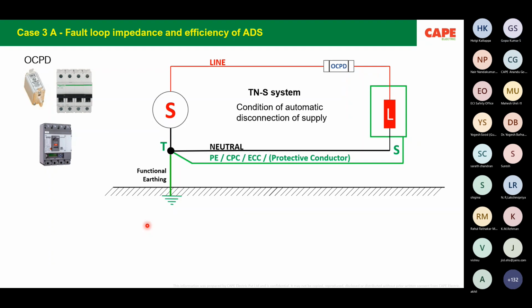For disconnection of a fault, we are supposed to use a protective device, because finally this device should trip. There are 2 points. I have put case 3A and case 3B. 3A is automatic disconnection, because the device should trip. And here the fault loop impedance comes into the picture. Fault loop impedance is here where I'm moving the cursor.